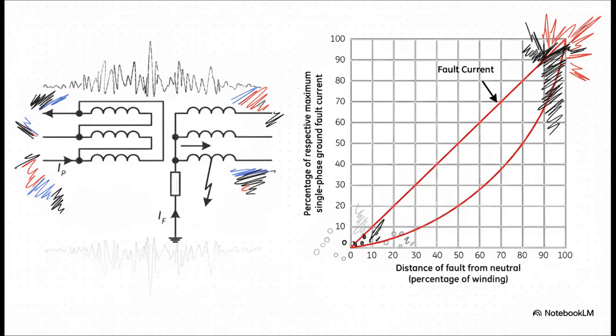But what happens if a fault is too quiet to hear? That's another challenge entirely. See, a transformer winding is connected to ground at one spot, called the neutral. And the weird thing is, the closer a fault happens to that neutral point, the less current it actually creates. It's like trying to hear a whisper next to a jet engine. Some of these faults can be so tiny that the main protection system might miss them completely.